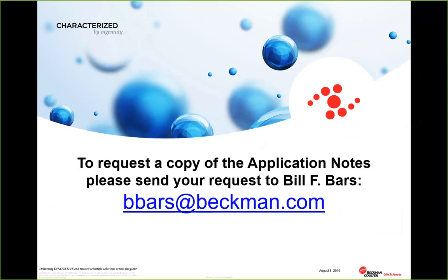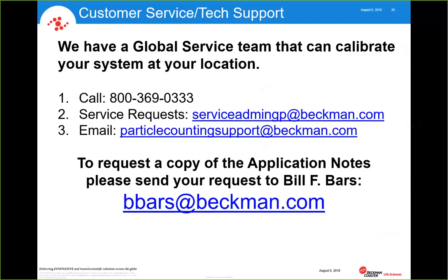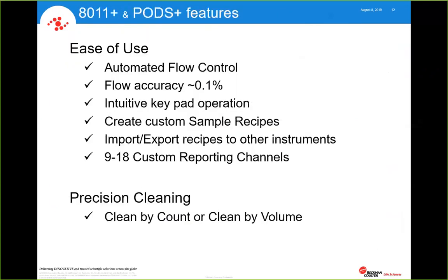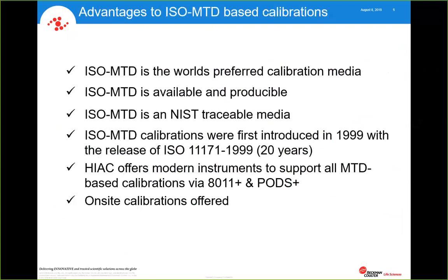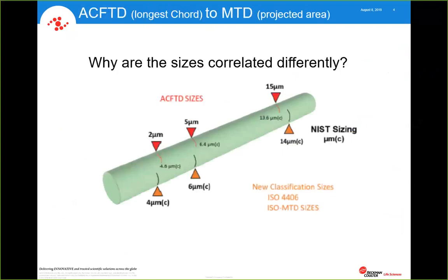You bet. Thanks, Jim, for that question. That's a great point. I'm going to cycle back toward the beginning of the presentation, where we showed why they're different. We talked about different sizing methodologies, but let me talk briefly about the reasons why we have to go from an HRLD 400 to a 100. The 400 sensor was originally designed for ACFTD calibrations. The minimum channel size was 2 micron, but mostly they were calibrated down to 5 micron. That was the first reporting size.